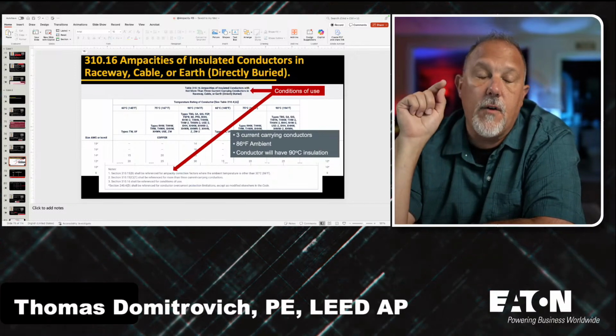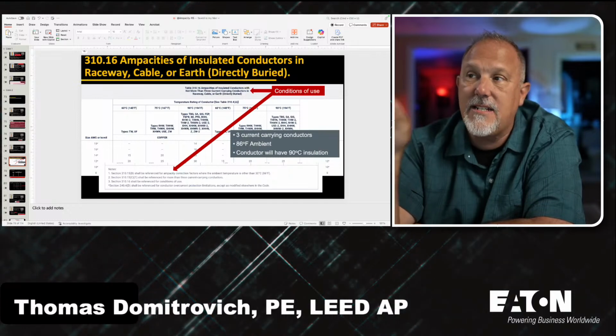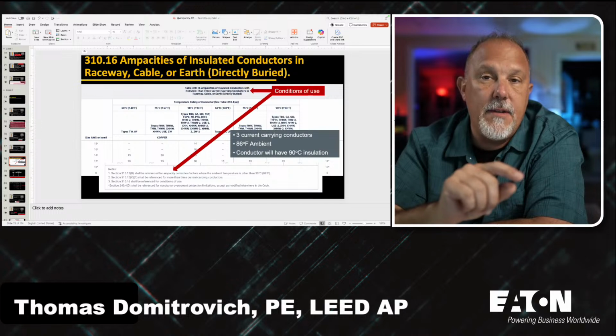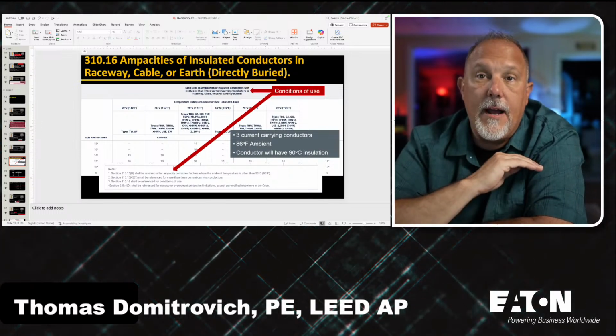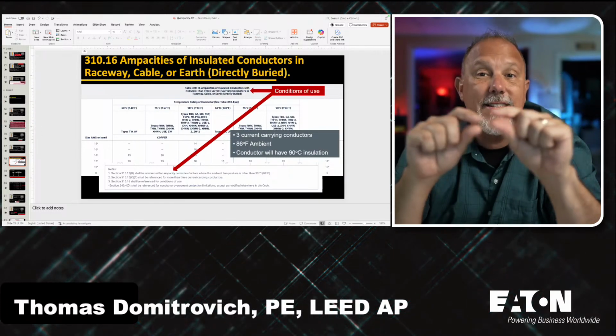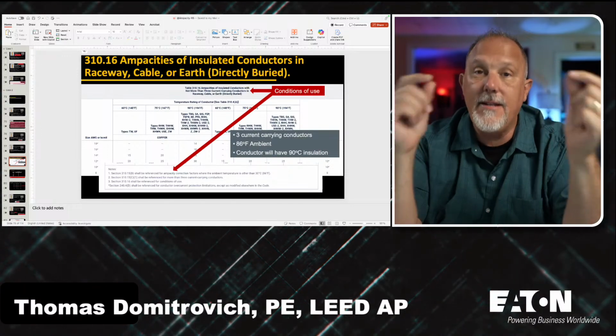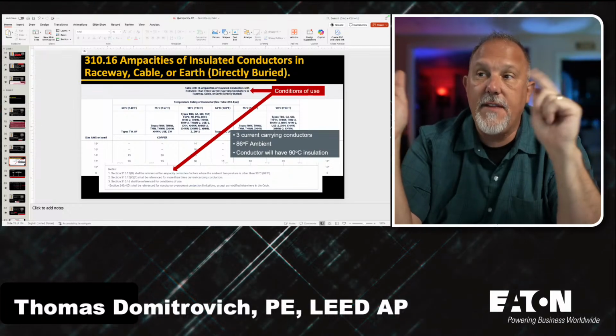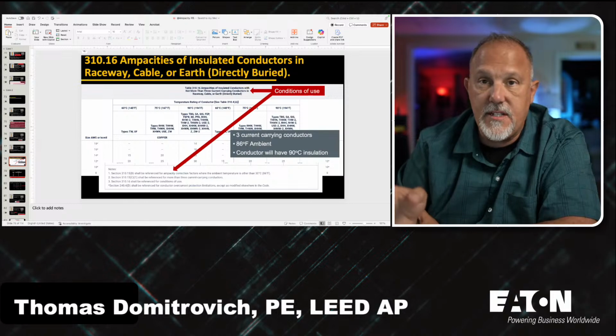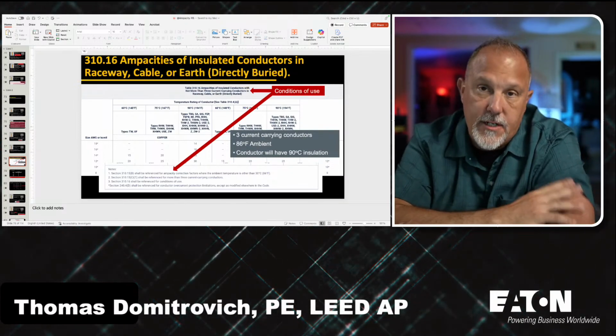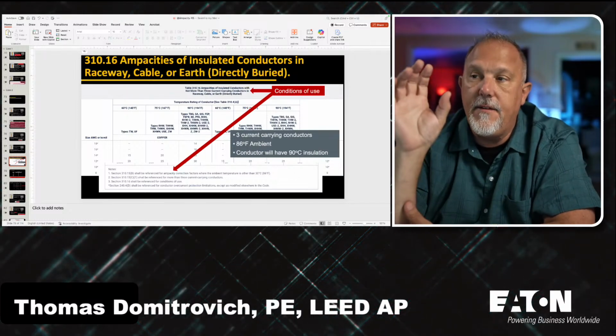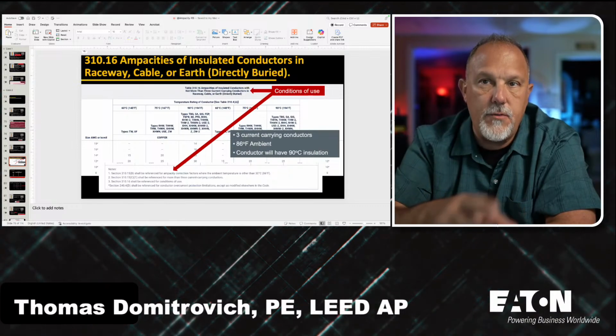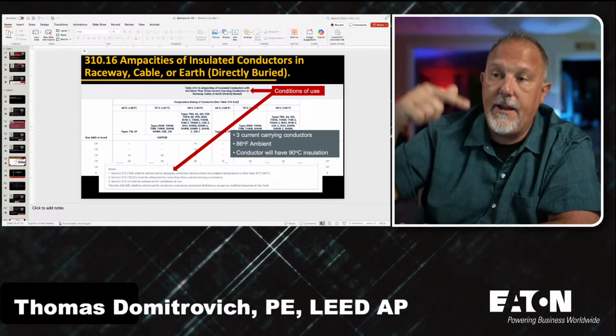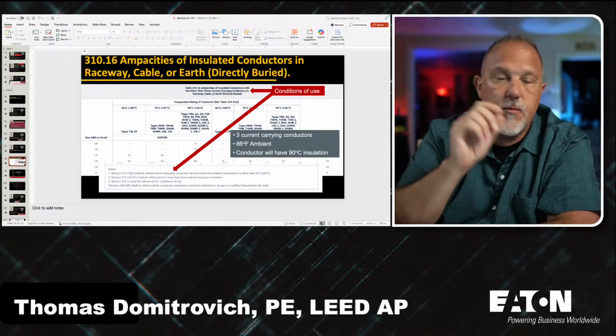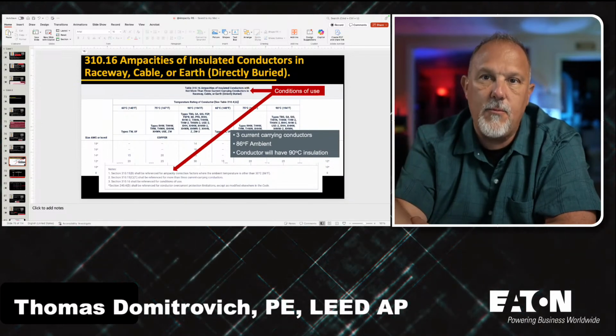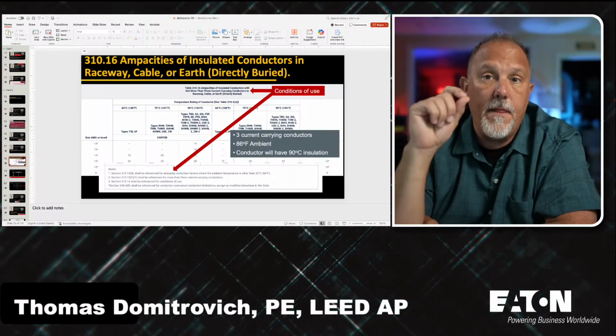Capiche? So what that means is for all of the conductors in 310.16, the ampacity shown under the 90 degree C column, I can carry that current every day of the week and twice on Sunday. I am golden with regard to the conductor. Now, we haven't talked about the terminations yet, but with regard to that conductor, I am within the constraints of the ampacity values of the 90 degree C column, for any one of those conductor sizes. We got that down. So we understand that the values of current in that table are based upon the conditions of use defined in the heading of the table and in the notes. And for any one of those columns, depending upon the insulation of the conductor, that conductor can handle that current all the time, continuously.